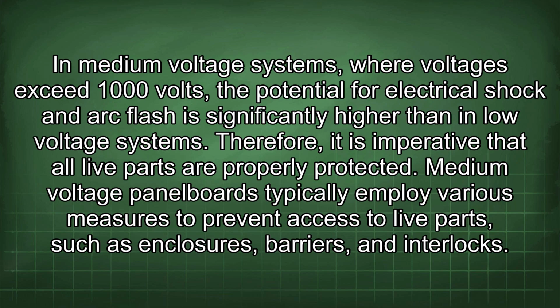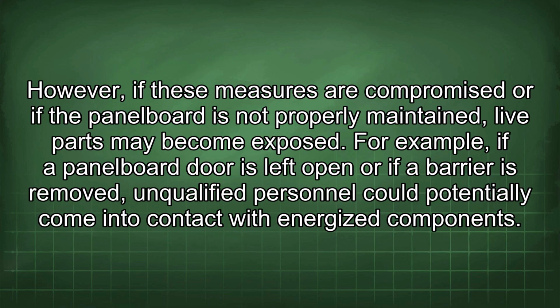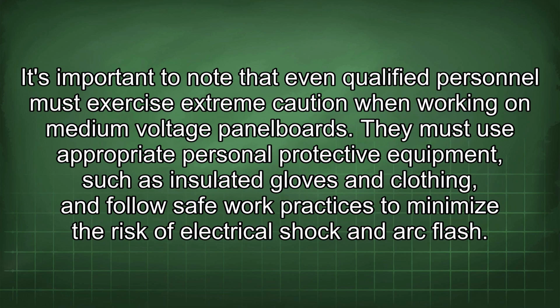Medium voltage panel boards typically employ various measures to prevent access to live parts, such as enclosures, barriers, and interlocks. However, if these measures are compromised or if the panel board is not properly maintained, live parts may become exposed. For example, if a panel board door is left open or if a barrier is removed, unqualified personnel could potentially come into contact with energized components. It's important to note that even qualified personnel must exercise extreme caution when working on medium voltage panel boards. They must use appropriate personal protective equipment, such as insulated gloves and clothing, and follow safe work practices to minimize the risk of electrical shock and arc flash.